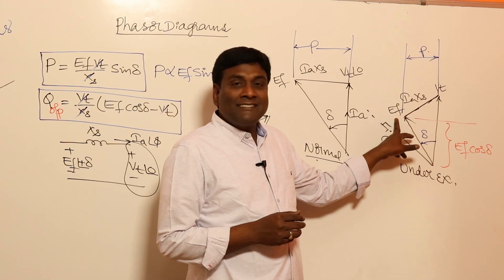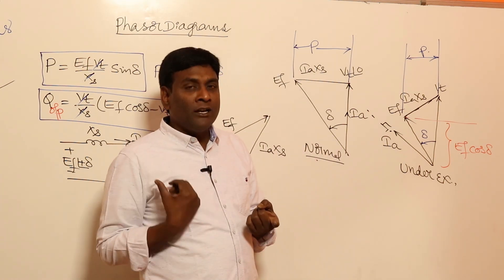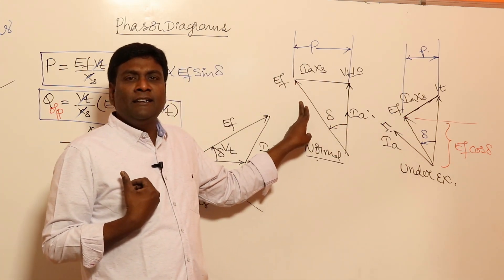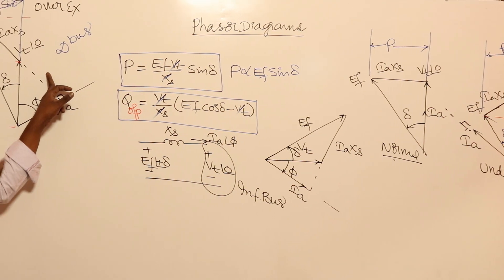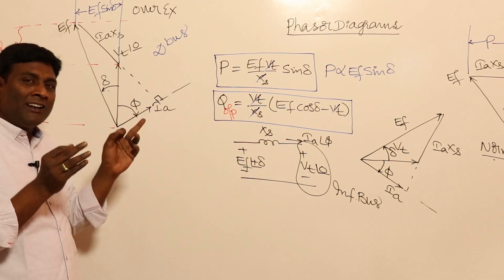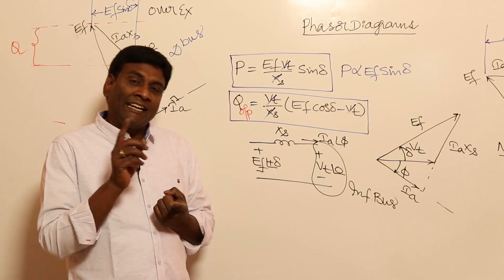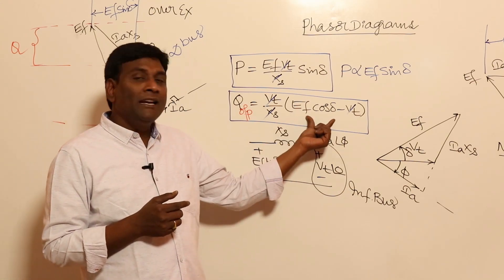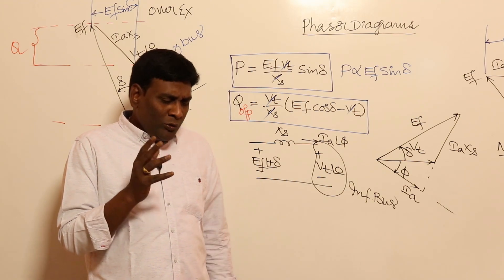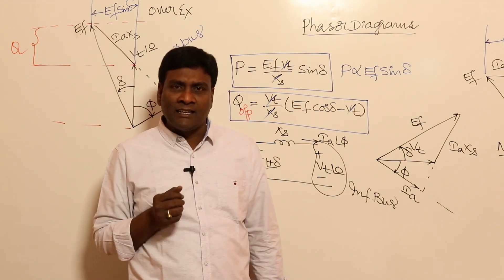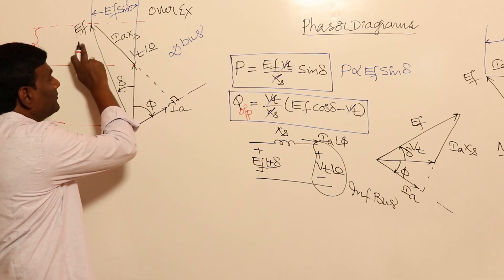So to summarize: in under-excited synchronous machine, it absorbs reactive power; at normal excitation, it neither delivers nor absorbs reactive power; and in over-excitation, it supplies reactive power. The fundamental takeaways are: Ef·sinδ gives information related to active power, and Ef·cosδ − Vt gives information about reactive power.